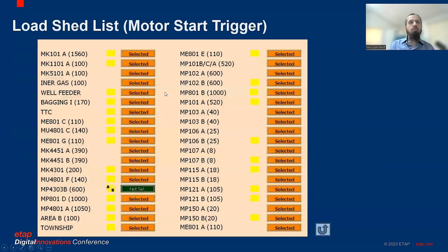This is a screenshot from the old system. You can see that this is the complete sacrificial load list, which is common for all the essential service motor triggers. Whenever an essential service motor starts, depending upon the rating of the motor and the status of the feeders, some of the loads in this list would get tripped. But the operator had no idea at any particular time that if I am going to start this motor, or if a particular motor comes online, what would be the exact load which will be shed in this scenario.